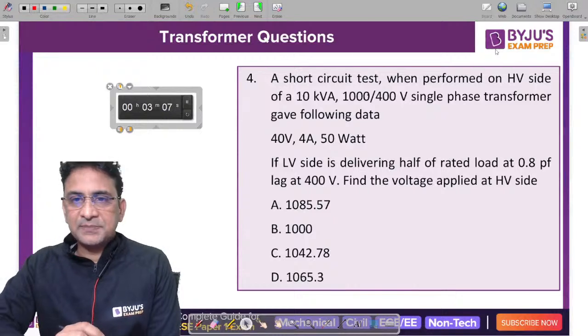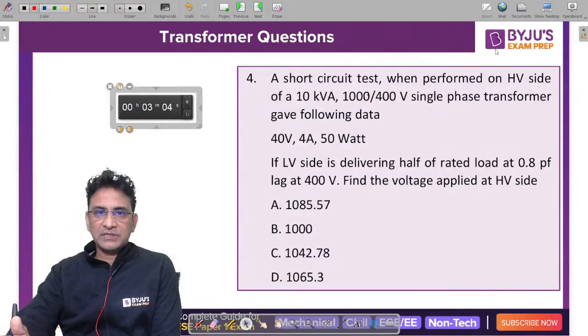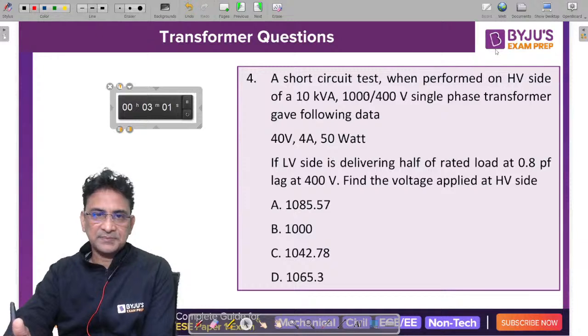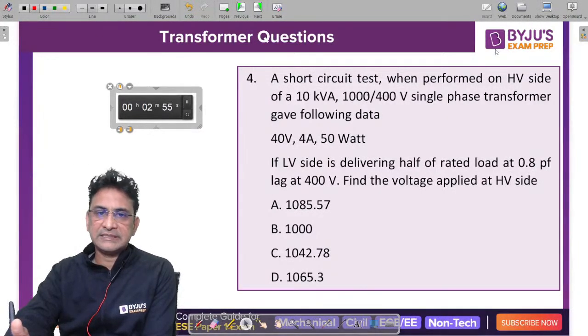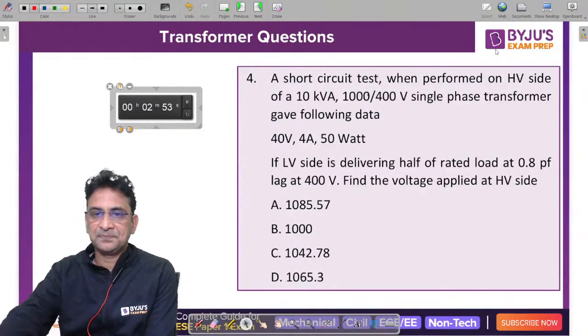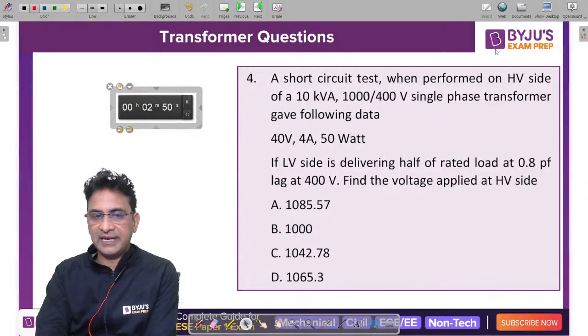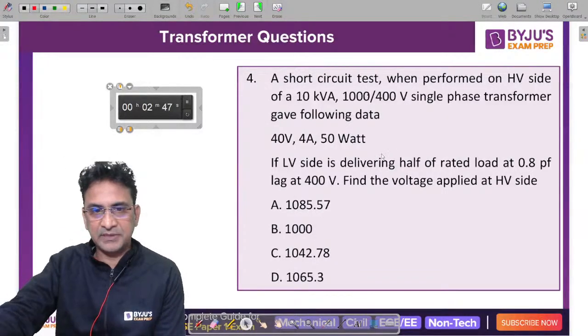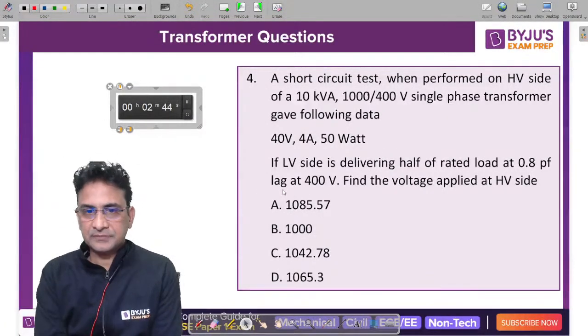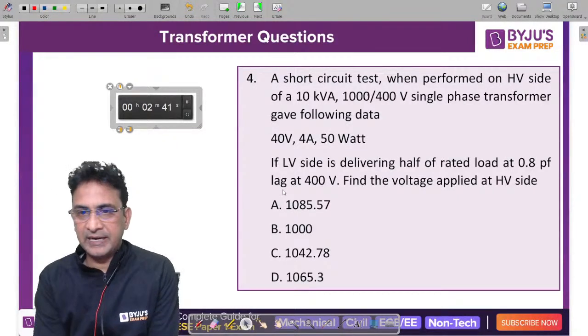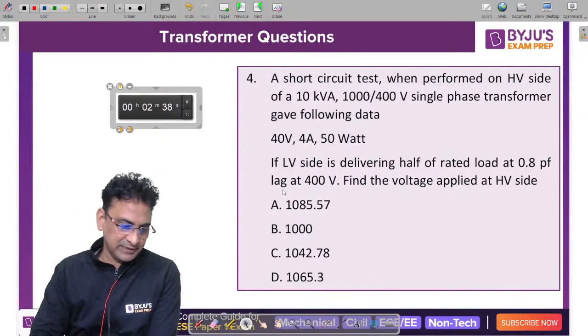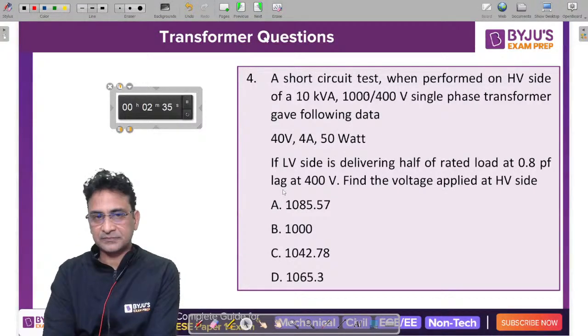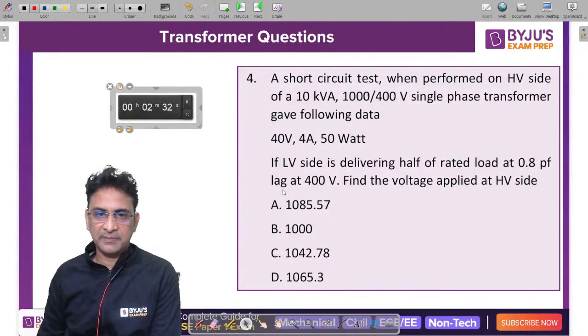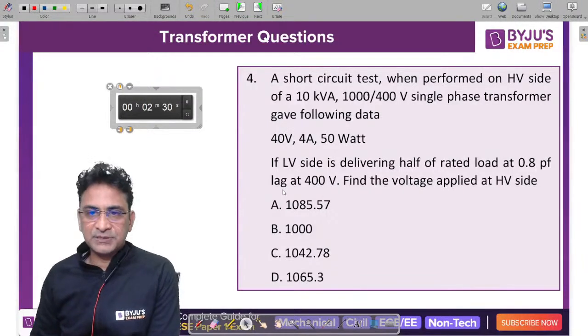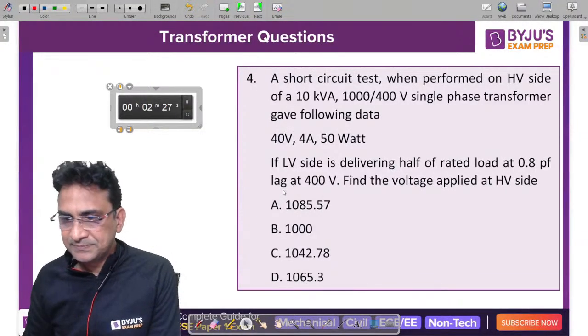The short circuit test is performed on the high voltage side of a 10 kVA 1000/400 volt single phase transformer. It gave the following data: 40 volt, 4 ampere, 50 watt. If the low voltage side is delivering half of the rated load at 0.8 power factor lagging at 400 volt, that means 400 volt is the terminal voltage, then what will be the voltage applied at the high voltage side? That is, how much voltage do you have to apply on the high voltage side so that you get 400 volt at the terminals of the low voltage winding at 0.8 power factor lag.